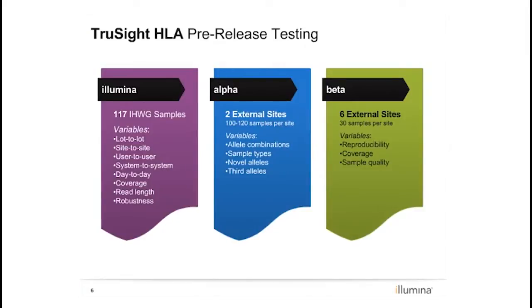We looked at novel alleles and some really challenging biology you wouldn't typically see — for instance, a third HLA allele present from a leukemic blast cell with a different HLA type. We were able to pick that up as well. After the alpha study, we went into a beta study with four additional sites. Each site performed at least 30 samples that they selected themselves, and we asked for broad representation of allele combinations and encouraged sites to throw hard samples at the assay.